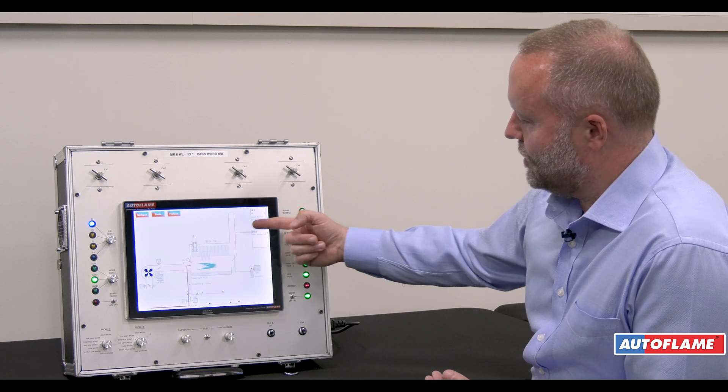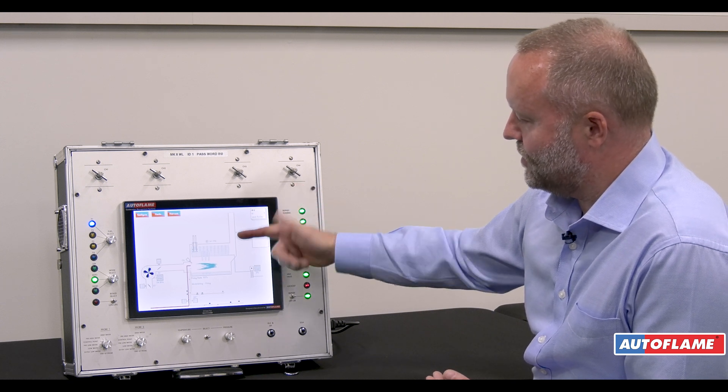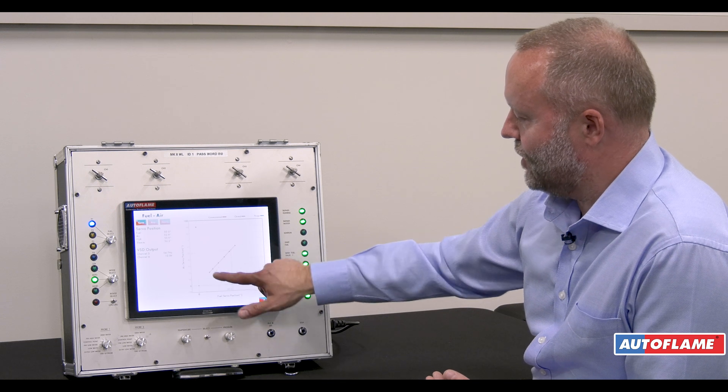Obviously if we measured the combustion at that point we'd have a very high oxygen level, meaning it would be impossible to set the fuel air ratio curve.